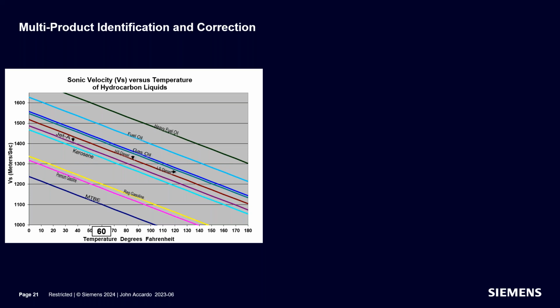Now, what our hydrocarbon meter does, amongst other things, it identifies what product is in your pipeline. But then it also has to correct for that particular product. Now, each of these products has a different viscosity value, has a different density value. And in most cases, when you're measuring flow in a hydrocarbon pipeline, you want normalized flow, or what is known as standard volume flow. So you want to correct the flow to what it would be at 60 degrees Fahrenheit, so that you're always comparing apples to apples. And that's a function of the fluid density and also the temperature. And the way that we identify a fluid is by its speed of sound. The speed of sound is its signature.